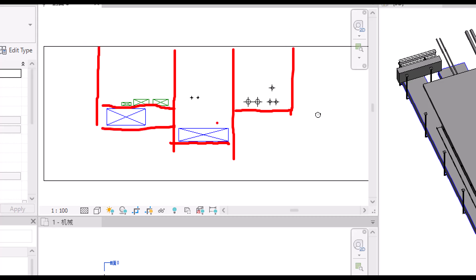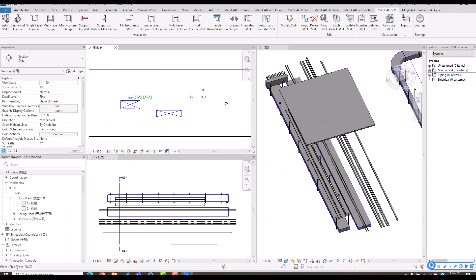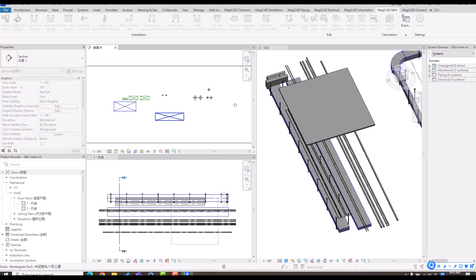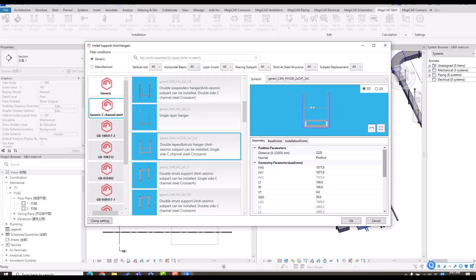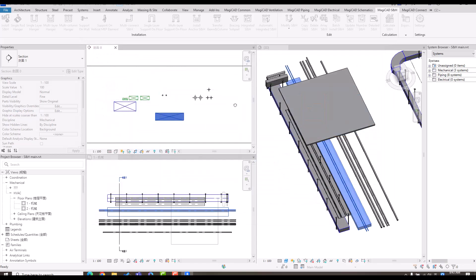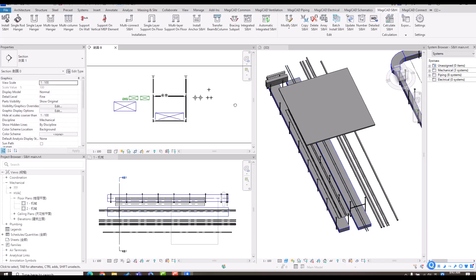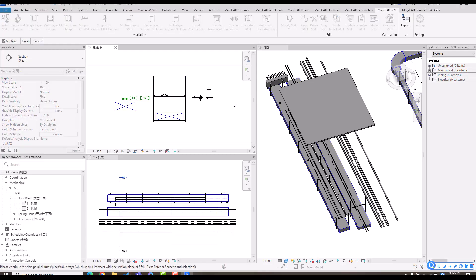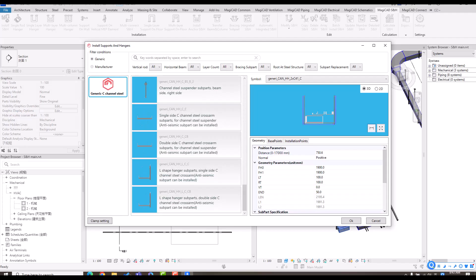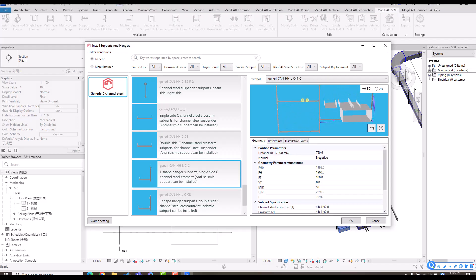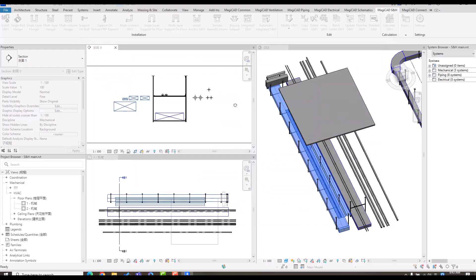To create an integrated support hanger, I select the install function and select the parts for the main section. I select the main support hanger combination — for example a double layer — and select the specification for the subparts, then click OK to get the result. After that, I use the integrated support hanger function, select the main part, select the elements, finish, then choose a different subpart. You can check the result in the 3D view and click OK to get the final result.